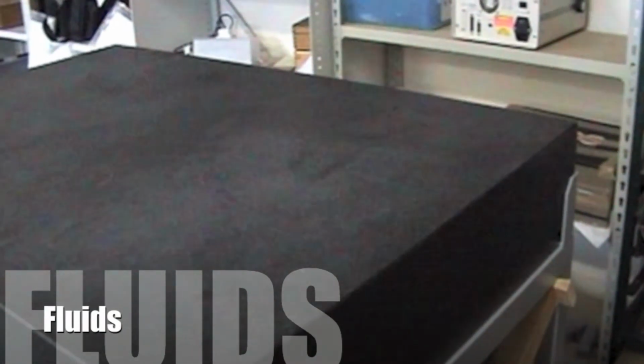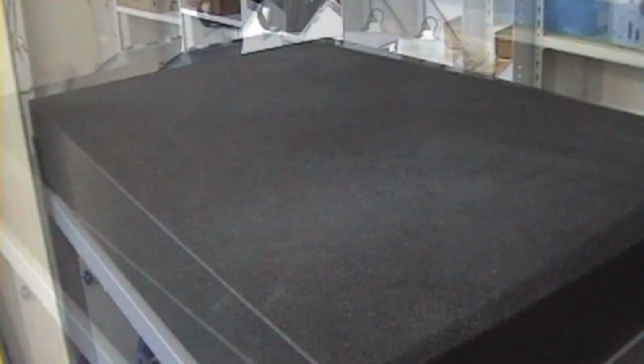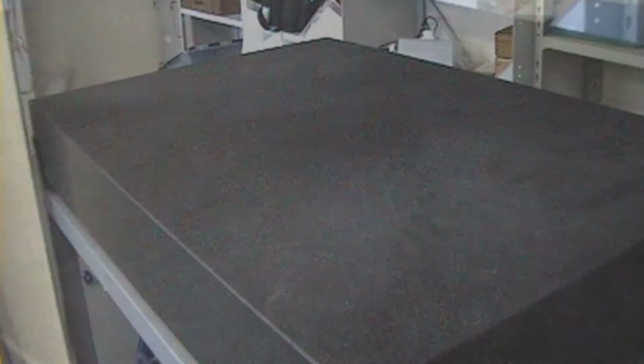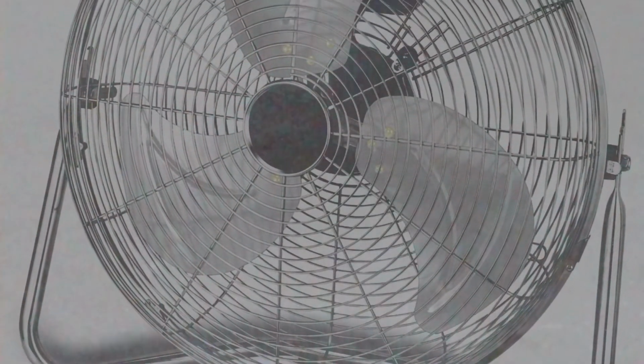Fluids. Make sure that people are using the correct cleaning fluids. Granite is porous, like a sponge. If you spill any fluid on it, it will soak it up and that will change the shape of the table. And finally, temperature. Make sure there are no great temperature gradients. For example, there are no fans nearby or no heaters nearby.